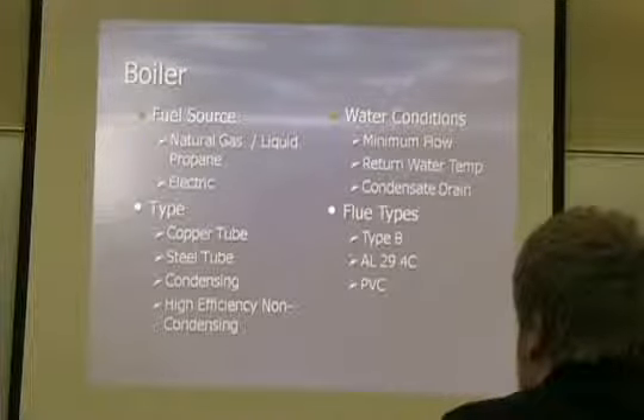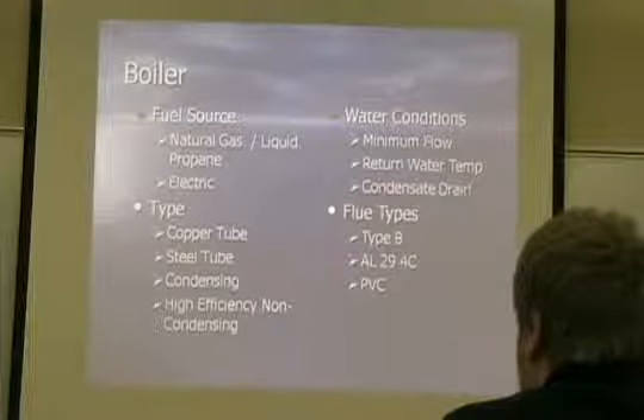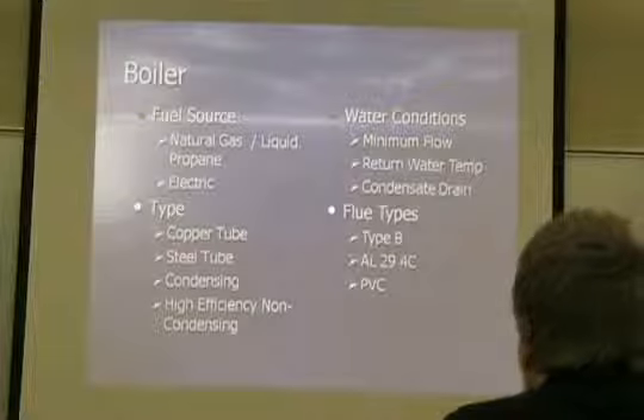the boiler is a sidearm application of your loop system. You don't run all your water flow through the boiler. That's just not necessary. So normally you just take a little water off the loop, heat it up, and inject it back into the loop at a very high temperature. It mixes with your loop temperature to maintain whatever loop temperature you're trying to maintain.